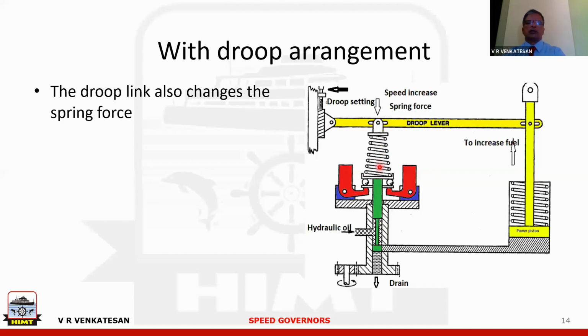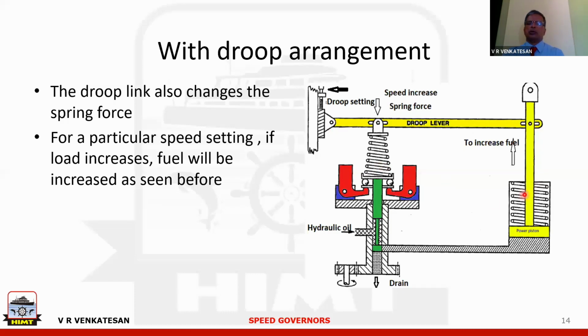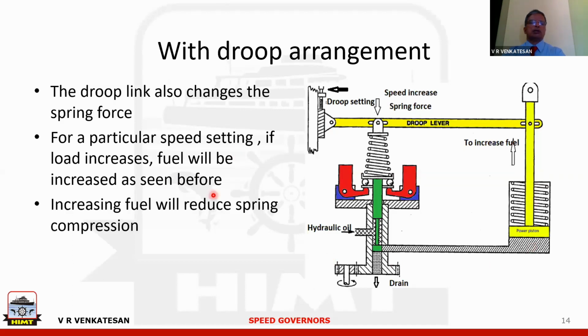So with increasing load, fuel will be increased as before. There is no difference in that. Fuel will once again be increased. But the spring compression will reduce now, and spring compression is the set point for speed. So what this mechanism is achieving is that with increased fuel or increased load, the speed set point is brought down.